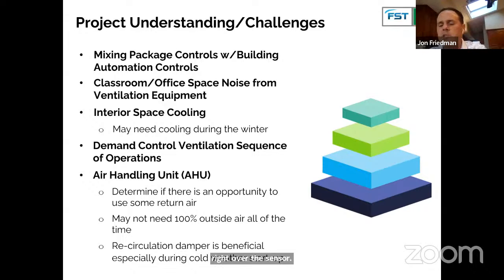So they know how to, if it's going to annoy the classroom, they're going to find a way to either complain or they get pretty creative and know how to bypass some of those systems, whether it's daylighting or an air conditioning system. So sometimes for these buildings, this would be like a larger building, typically a high school. If there's some interior office spaces, a lot of times they shut off all the cooling for the building, but there's higher heat loads, maybe it's a room with copy machines or a computer type room, but that would get caught early on in design. If you have a VRF system, this would not be an issue because the system can do cooling and heating at the same time.